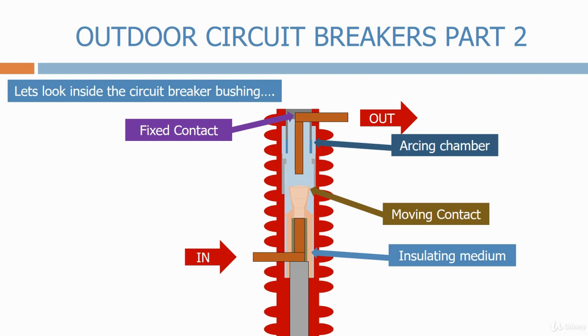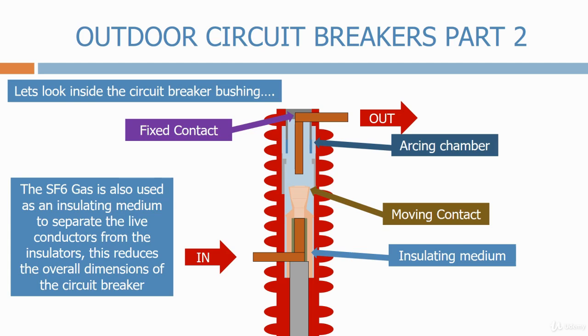Let's now open the circuit breaker. When the moving contact changes position, the pressurized SF6 gas floods into the arcing chamber, increasing the dielectric strength between the circuit breaker contacts and quenching the arc. The SF6 gas is also used as an insulating medium to separate the live conductors from the insulators. This reduces the overall dimensions of the circuit breaker.